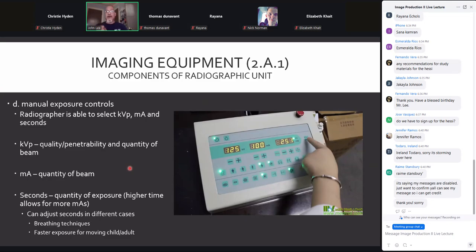We need a high current. kVp, of course, determines the quality, penetrability, and it affects the quantity of our X-ray beam. The more energy and kinetic energy those electrons have, the more likely it is for them to have multiple interactions at the target. The more interactions they have, the more X-rays we produce. Therefore, quantity goes up. mA merely dictates the quantity of X-rays in our X-ray beam.